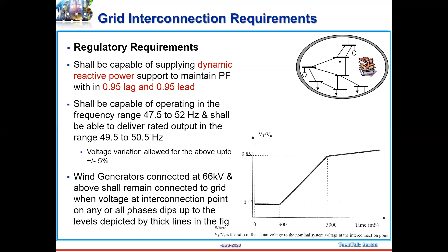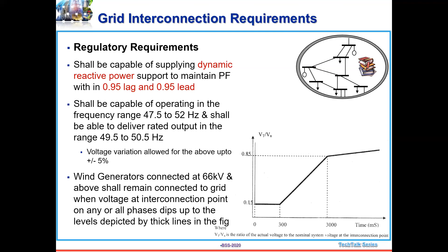For wind generators, there is a special condition for generators at 66 kV and above. They should remain connected to the grid when the voltage at the interconnection point on any or all phases dips to the levels indicated by the thick lines, that is between 0.15 and 0.85, 15% to 85%. For a time of 300 milliseconds to 3000 milliseconds, they should remain connected to the grid. That is the condition.